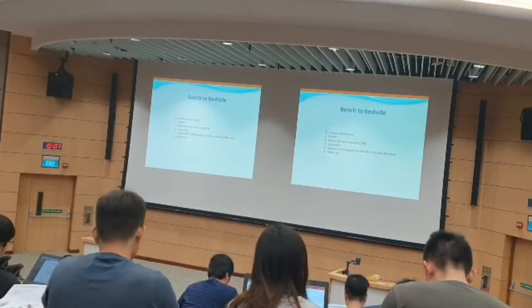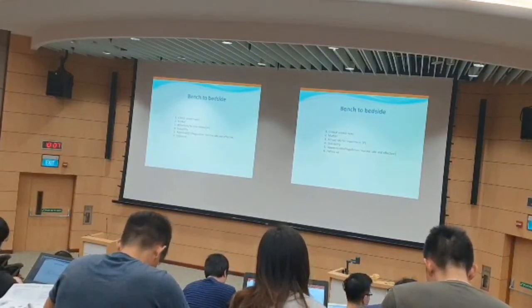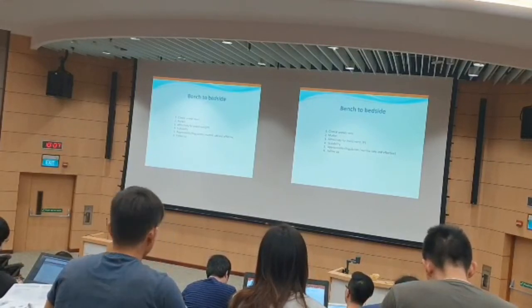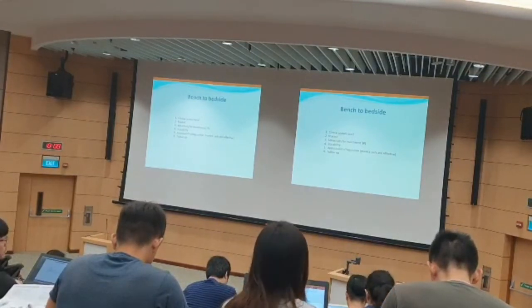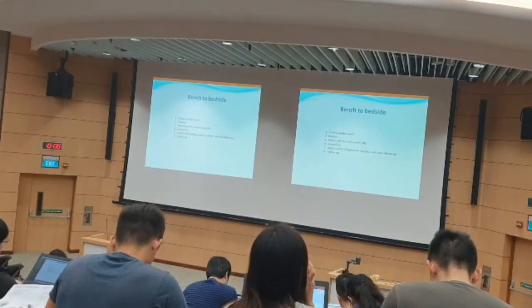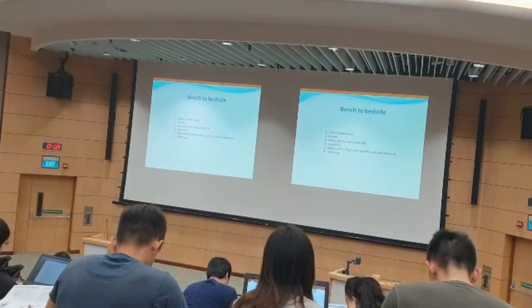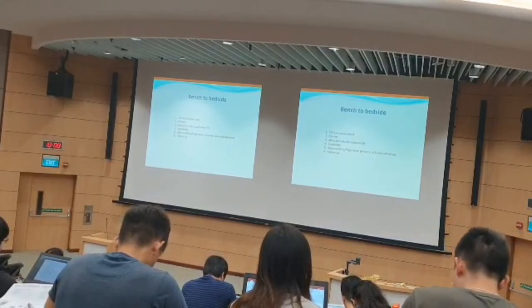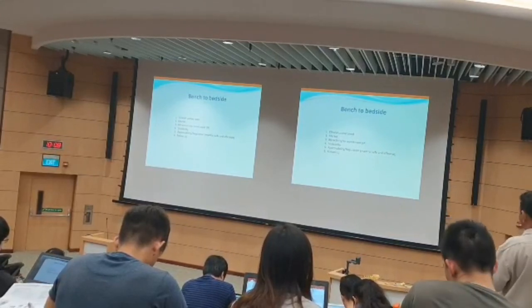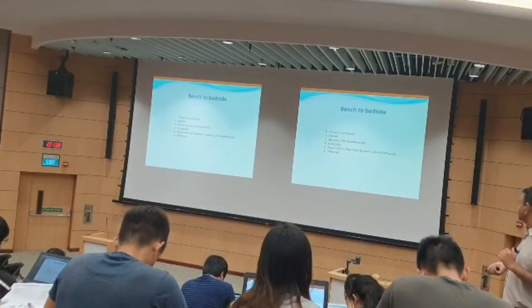Okay, so this is something they will look for. And also, if you claim that your device can perform a particular function, how will you ensure that? Show me the evidence. It's all about evidence. Show me the evidence that it is effective, that it is performing its intended function. A cardiovascular stent is supposed to perform like a cardiovascular stent. It's supposed to have a certain function, right? So you have to define the function, and you have to provide the evidence by different kinds of experiments to show the FDA or HSA that it is actually doing what it is intended to do. Okay. So safety and effectiveness is very important.